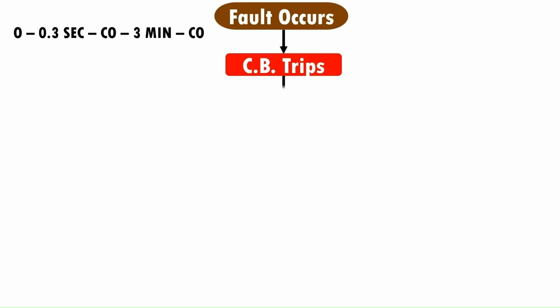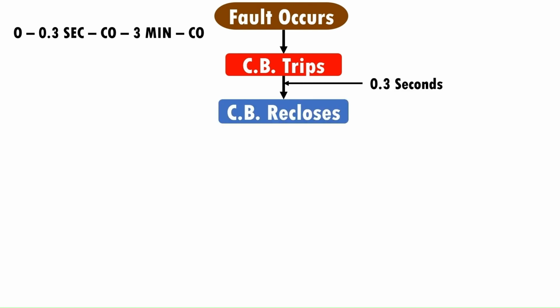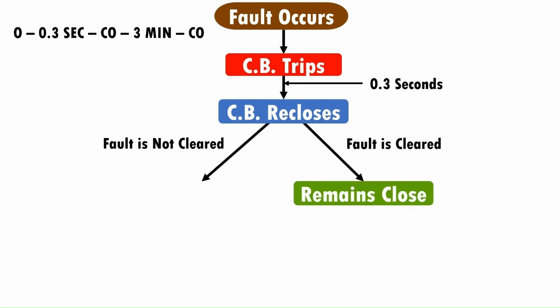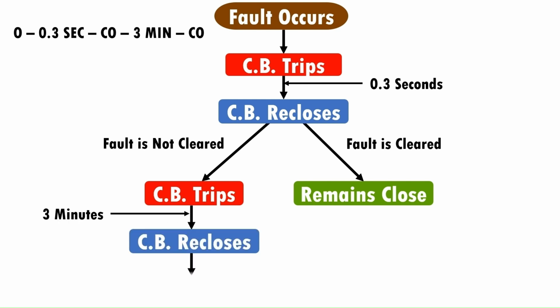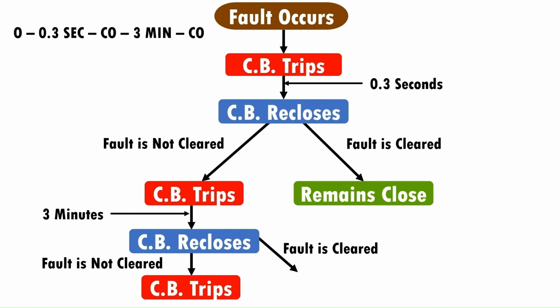When a fault occurs, the circuit breaker will trip and open its contacts. And after 0.3 seconds, the auto recloser will close the contacts automatically. Now if the fault is cleared, then the circuit breaker contacts will remain closed. But if the fault is not cleared, then the circuit breaker contacts open again. After 3 minutes, the auto recloser closes the contacts of the breaker automatically. And this time, if the fault is not cleared, then it will open and remain open. But if the fault is cleared, then it remains closed.